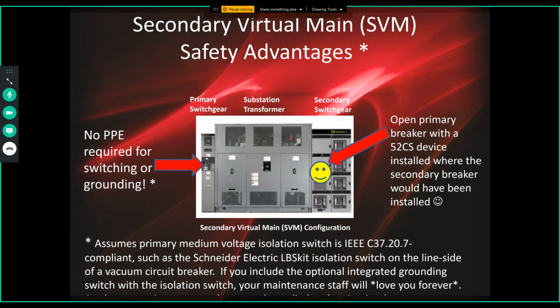Because when you are used to getting into category 4 PPE, opening up the equipment, verifying absence of voltage with medium voltage test device, attaching a ground cable manually with your hand, getting out your hot stick and manually attaching the 3 grounding cables in order to establish an electrically safe working condition, you've placed yourself at risk. It's hot, it's uncomfortable, and it takes a long time. In comparison to a completely safe operation, which, no exaggeration, takes less than 10 seconds.